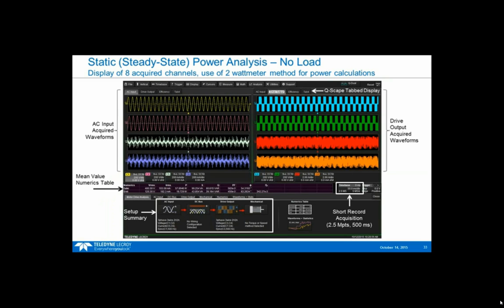So this is a screen capture from our motor drive analyzer. This is what I call the static or a steady state power analysis. There's no load applied right now. There's 8 channels acquired. We're using a 2 watt meter method for the power calcs. Everything on the left here, you see this tab, it says AC input. These are all the AC acquired waveforms. I have 2 voltage and 2 current. That's how the 2 watt meter method works.